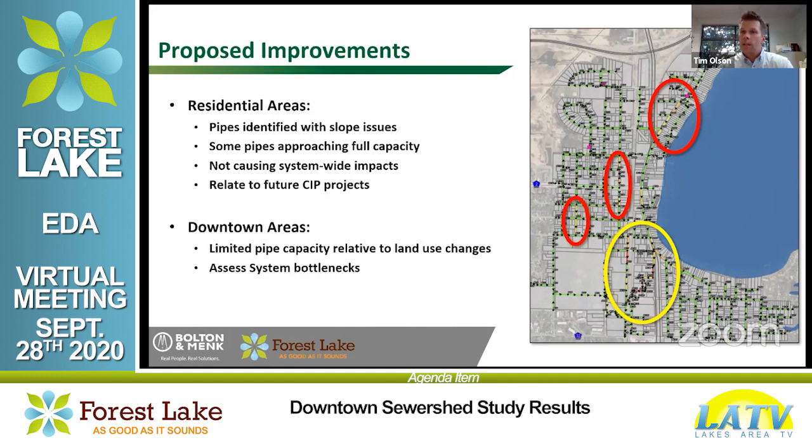The red circle on the north is of particular concern because there's a sanitary flow lift station at the north end of that run, that may have the ability to take some additional flow later on as land use changes. So there's a commercial industrial property that's even further north that's kind of outside of the study area. We wanted to make sure that we looked at that particular pipe segment because it's essentially nearing its design capacity right now. So that might be something that has to be looked at as redevelopment occurs.